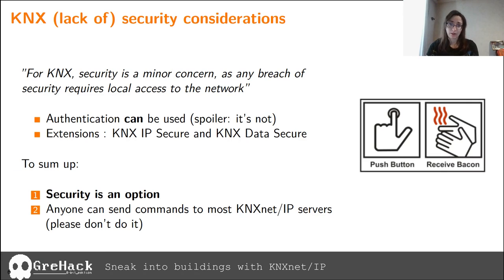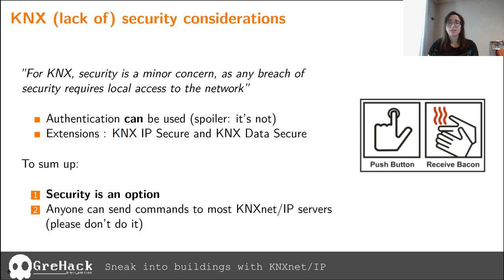You may have noticed that I was able to change the value without authenticating in any way. There are a few things to say about KNX cybersecurity. The standard explicitly says that the security of KNX relies on its low exposure, which is a bad idea considering KNXnet/IP. Authentication is not mandatory. There are extensions for KNXnet/IP frame transport security that manufacturers are free to implement or not, so cybersecurity just looks optional. For instance, my test device for this talk implements authentication, but it's not enabled by default, and apparently this is quite a common setting that does not seem to be changed much.